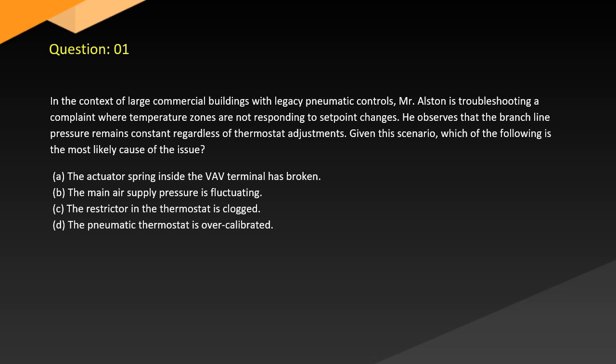A. The actuator spring inside the VAV terminal has broken. B. The main air supply pressure is fluctuating. C. The restrictor in the thermostat is clogged. D. The pneumatic thermostat is overcalibrated.